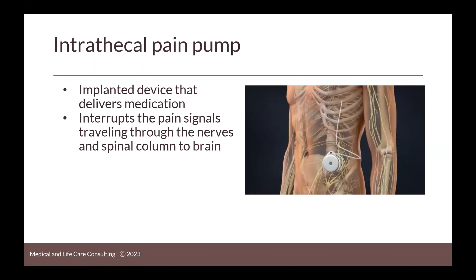So how does it work? The pump is refilled in the physician's office every 2 to 3 months, depending on the use and the size of the reservoir. And that's determined by the physician's office. The residual medication is removed from the pump and the new medicine is put in. The pump is set and adjustments to dosage are done at that time. An alarm date is determined, and this is the marker for getting the pump refilled. Most physicians require that it gets refilled 2 weeks before the alarm date, as if the medication runs out, it can cause a severe problem.